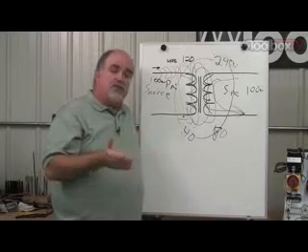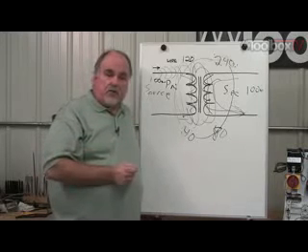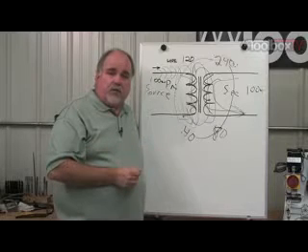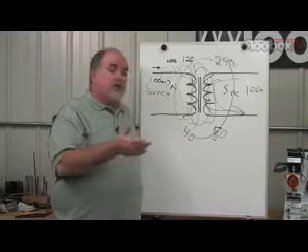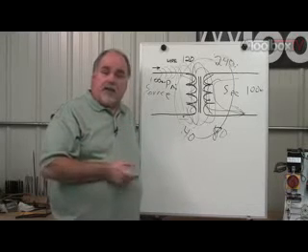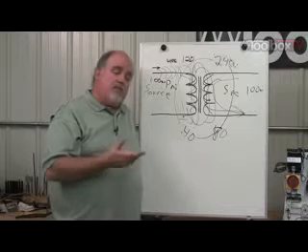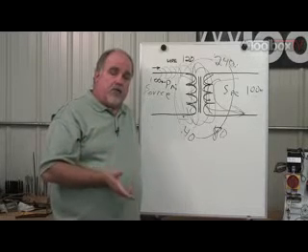So when the power gets near your home, for instance, a small substation your local utility has, that 500,000 volts would get stepped down to something more reasonable, 50, 70,000 volts, something like that. Then as it got nearer your house, they'd step it down to maybe 13,800 volts, and then that might be what is feeding the transformer on the utility pole outside your home.